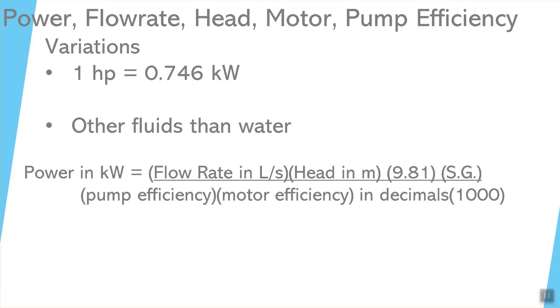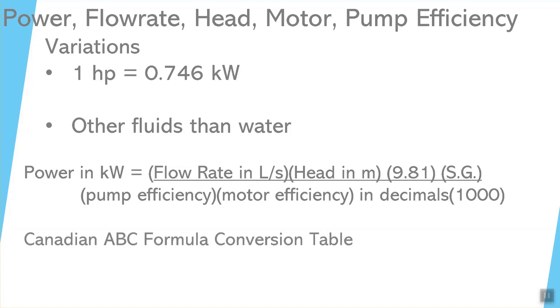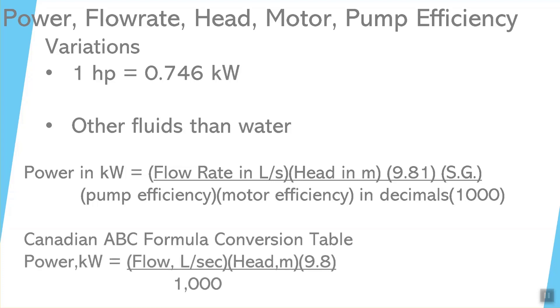Now that we've finished that formula, there's an additional one worth referencing — from the Canadian ABC formula conversion table that would appear on your class 1 through class 4 water or wastewater exam. It's a little simpler: power in kilowatts equals flow in liters per second times head times 9.8, divided by 1,000. However, this formula does not include pump and motor efficiency, which are in a separate formula on the sheet. You have to combine those two formulas yourself, and the full formula with flow rate, head, 9.8, divided by efficiency, efficiency, and 1,000 will cover that.